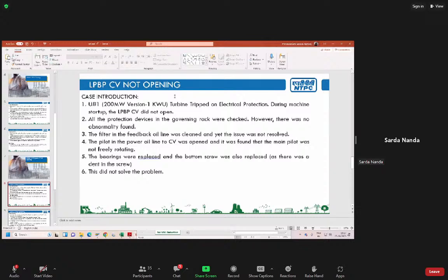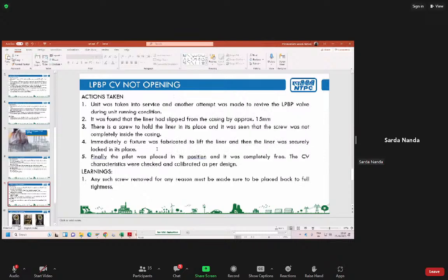Unit 1 had tripped on some electrical problem, and during unit startup, the LP bypass valve did not open. All protection devices were checked. There was no problem found. We checked the filter line in the feedback oil, but that was also not the problem. The pilot was clean, but it was not rotating freely.